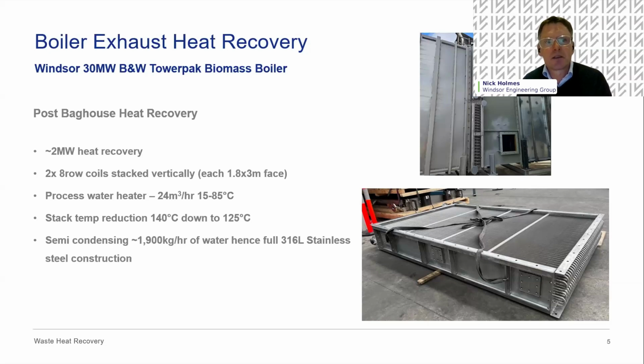So in this instance, a 30 megawatt boiler, it's a biomass boiler. The standard flue temperature is already low at about 140 after the economizer and an air preheater. But we managed to drop that down to 125, which doesn't sound like a lot, but with a 30 megawatt exhaust stream, that's a lot of energy. So in this application, we recovered 2 megawatts of medium grade hot water that could be used in the process.